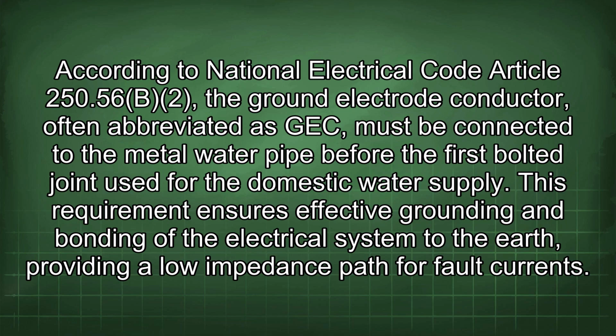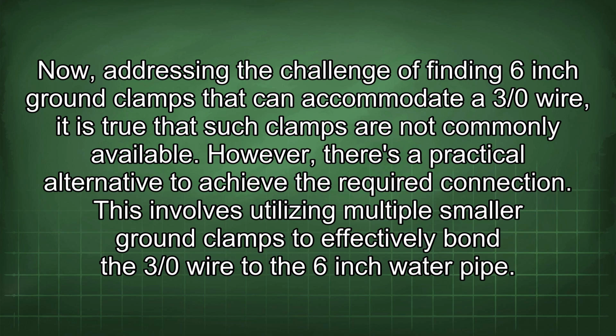fault currents. Now, addressing the challenge of finding 6-inch ground clamps that can accommodate a 3/0 wire, it is true that such clamps are not commonly available. However, there's a practical alternative to achieve the required connection. This involves utilizing multiple smaller ground clamps to effectively bond the 3/0 wire to the 6-inch water pipe.